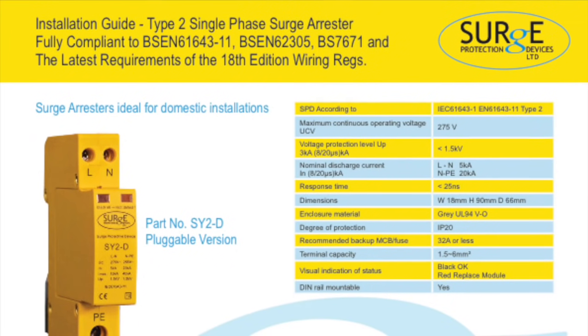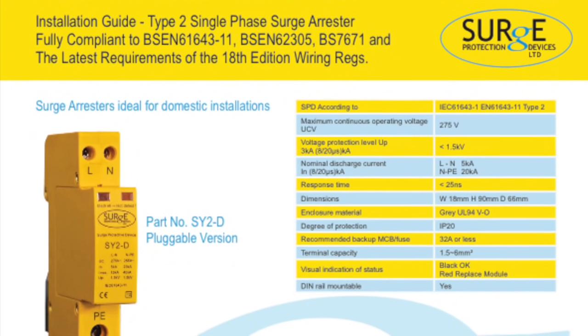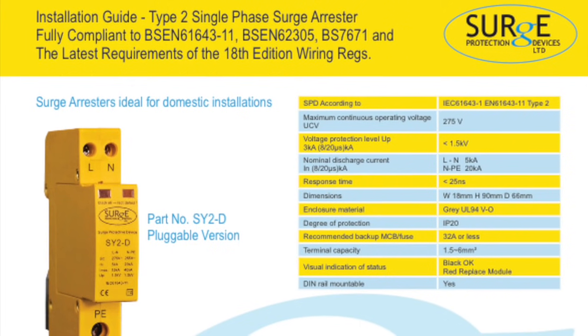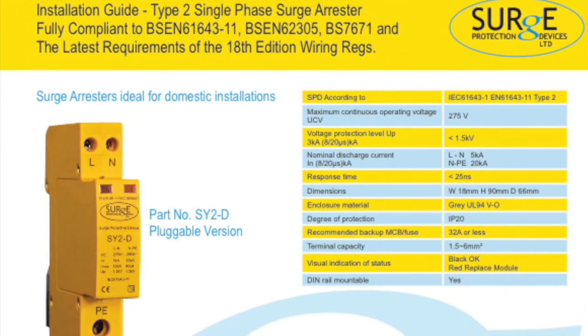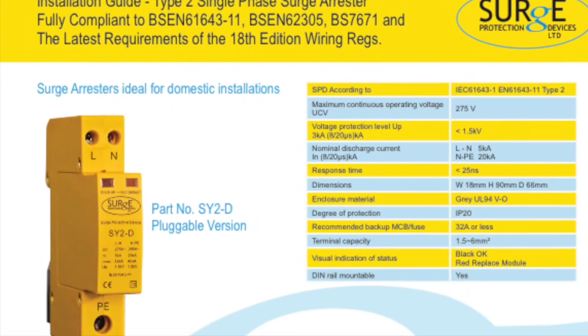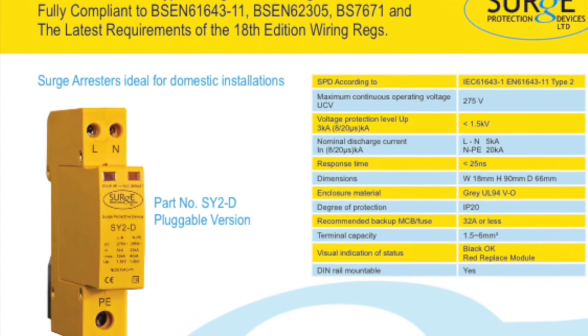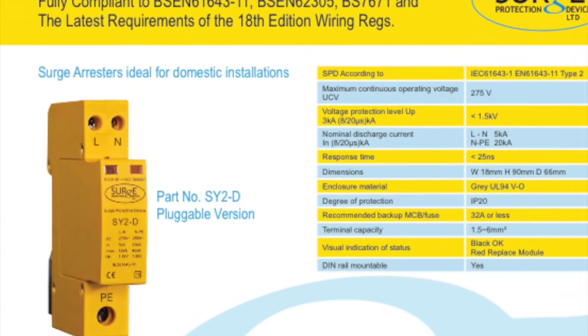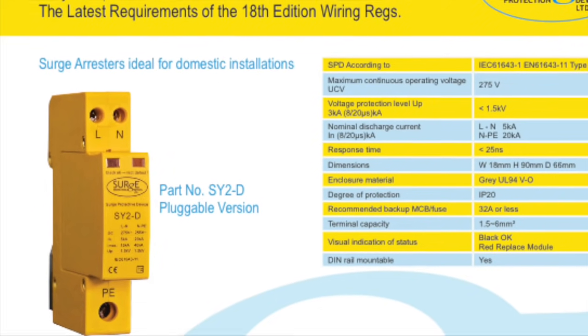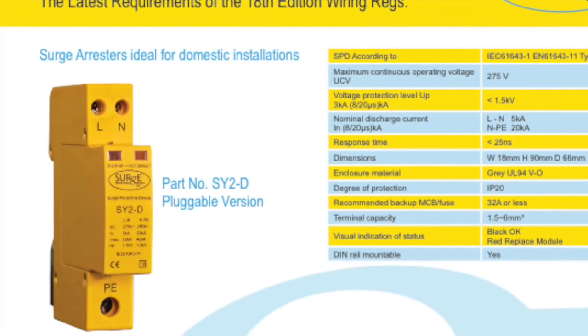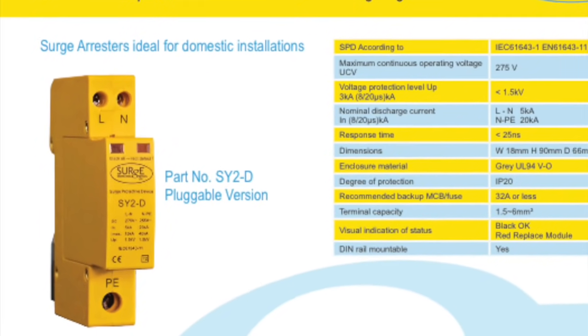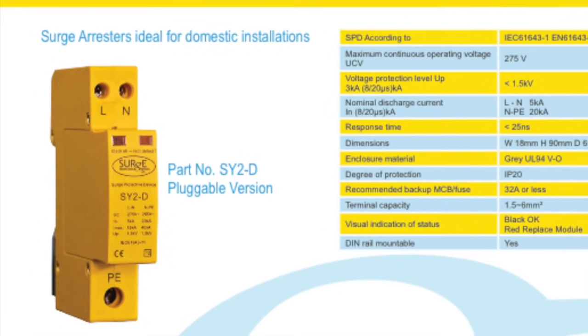So enough with the maths, let's have a look at the SY2-D and how to install it. Unlike arc fault detection we were playing with in a previous video, which is applied to individual circuits, a Type 1 or Type 2 surge protector is connected in parallel with the entire installation, meaning only one needs to be fitted. In the case of this Type 2 model, it's the size of a standard MCB and so can sit on a DIN rail at the CU.